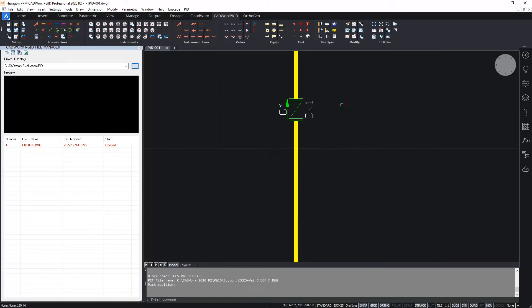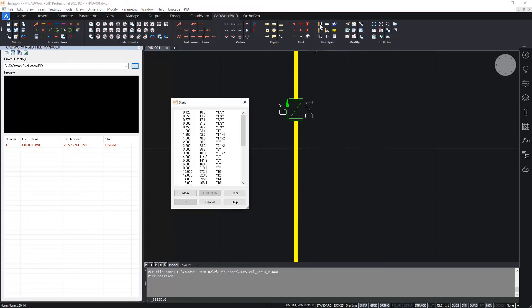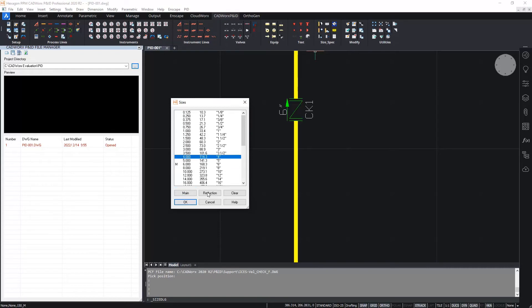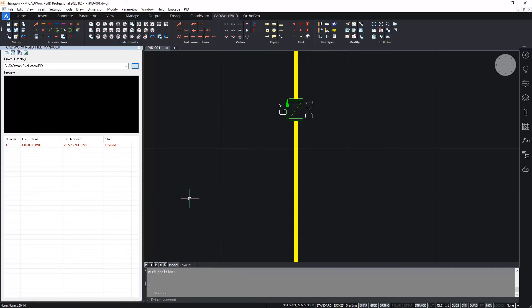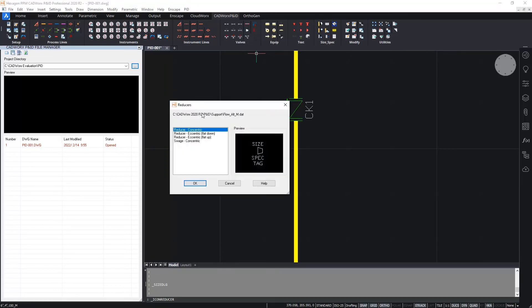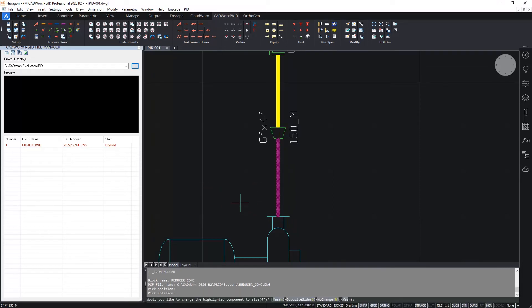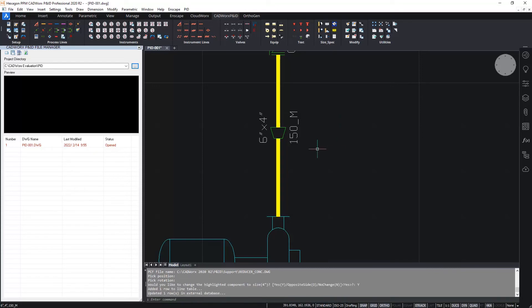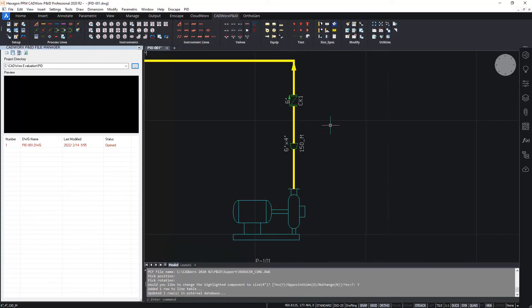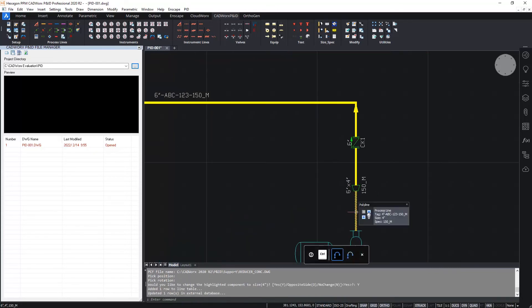Next I'm going to place a reducer. Before I place the reducer, I'm going to set the main and reduction sizes. So I'll set a six inch main size and a four inch reduction size. And then on the reducers icon over here, I'm going to select the reducer, pick the concentric reducer symbol from the library, and insert this close to the pump discharge nozzle. Picking the direction. When I place the reducer, I then get a prompt from CADWorx saying, would you like to change the highlighted components, which is just this small section of pipe, to the reduction size, four inch. And I will say yes. This is now, from the tool tips as we can see, four inch line.